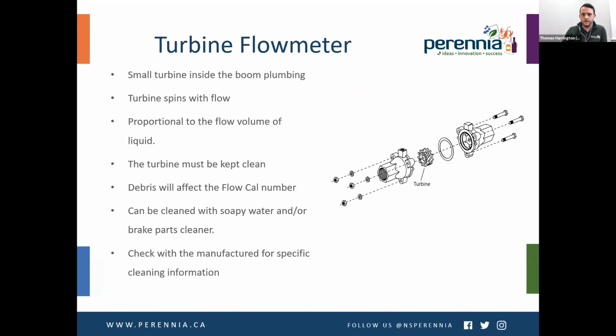And this is a standard turbine flow meter. There's a small turbine inside the boom, and as the flow passes through the boom, the turbine spins, and the speed at which it spins is proportional to the liquid volume flow through the boom. As I mentioned, it's very important to keep this clean, as any sort of debris is going to affect how fast the turbine spins, and that's going to affect your flow cal numbers. So you can clean them with soapy water. It's going to depend on the manufacturer's recommendations, but they might also recommend using something like a brake parts cleaner or something like that.